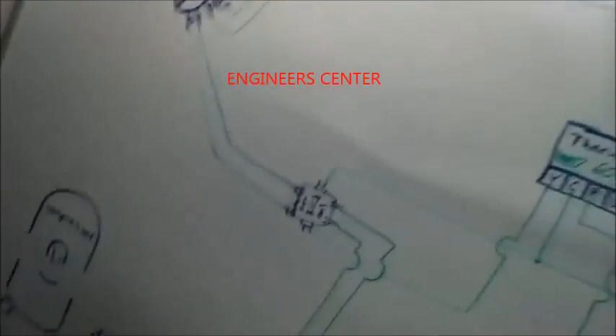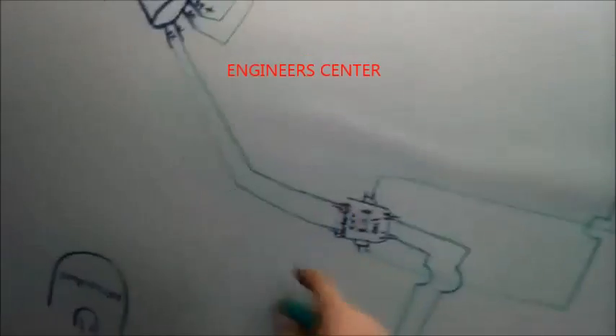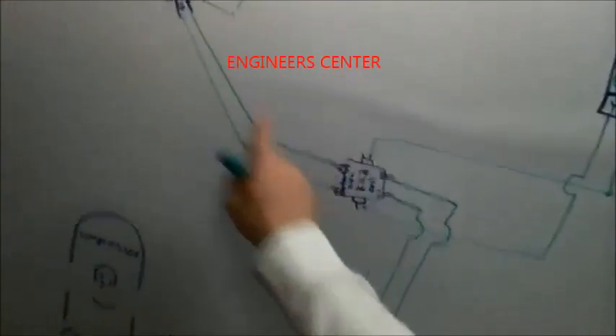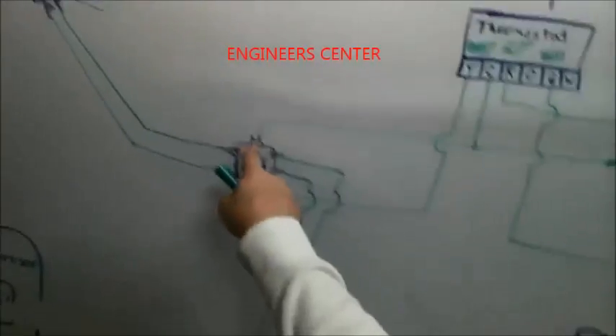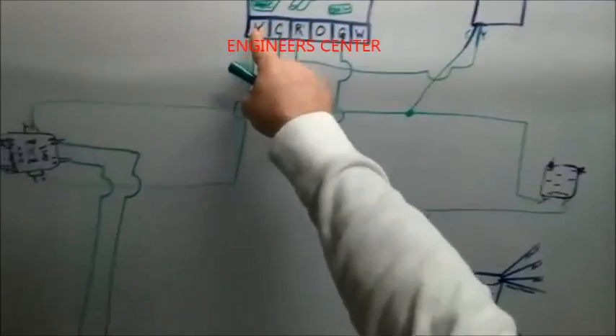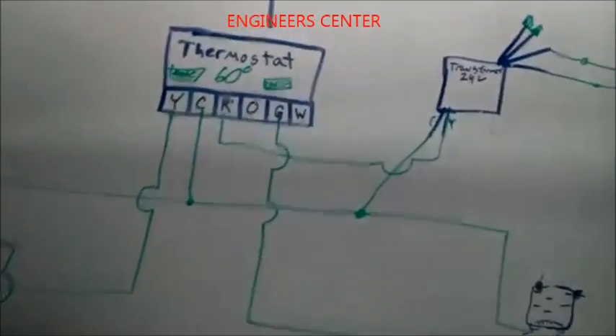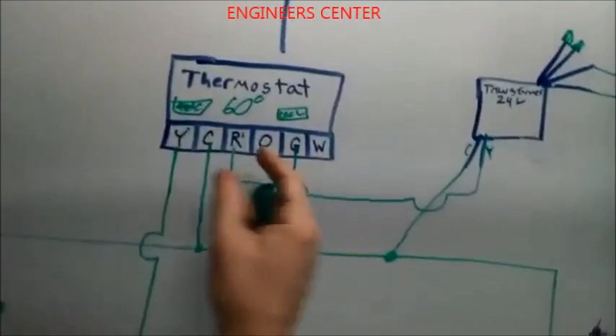Very basic and easy. Now this thing, when this is open, it's going to be off. When it closes, it's going to be on. What closes it? Well, yellow does, because it's already got common at all times. So all you got to do is close the thermostat, or turn the thermostat on. It will close red and yellow, close your contactor, turning on your condenser motor.